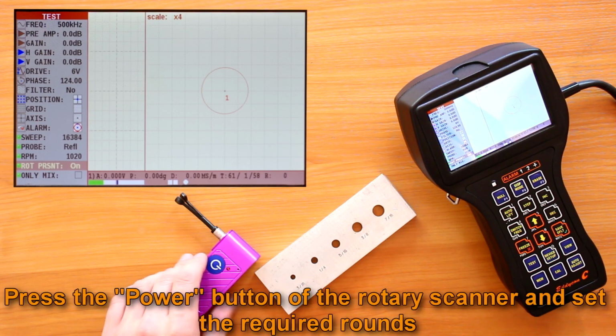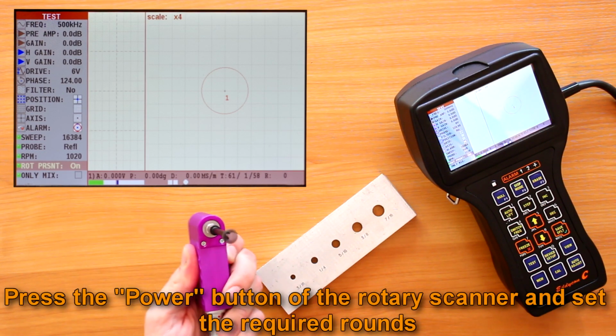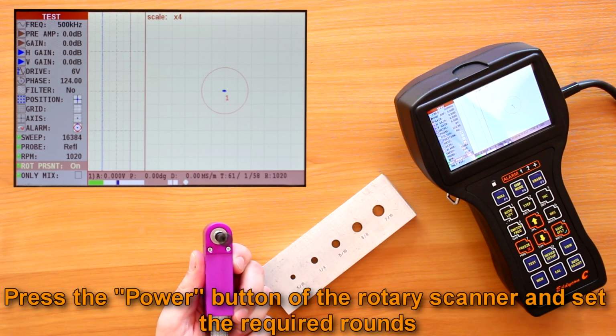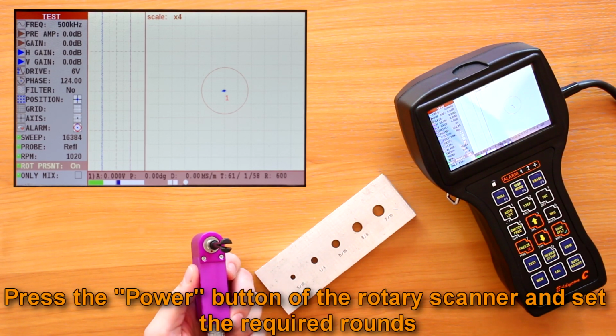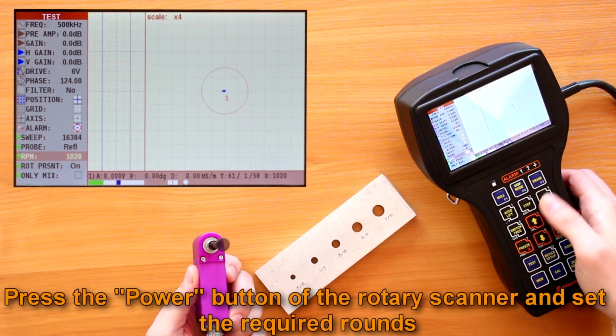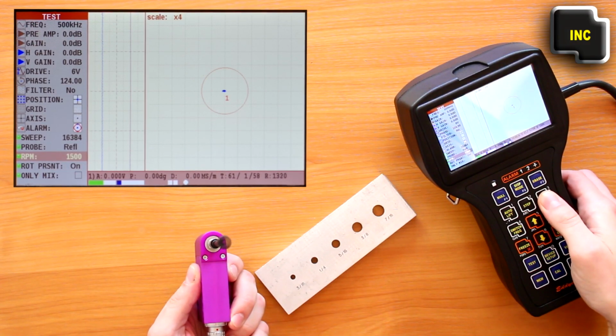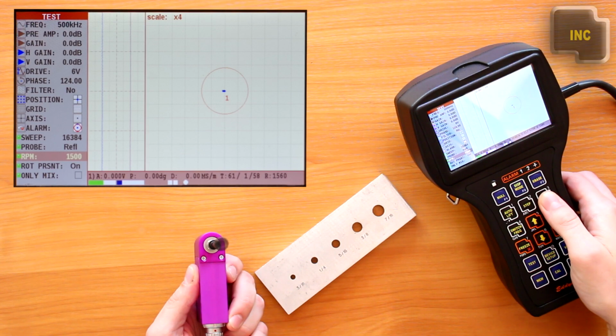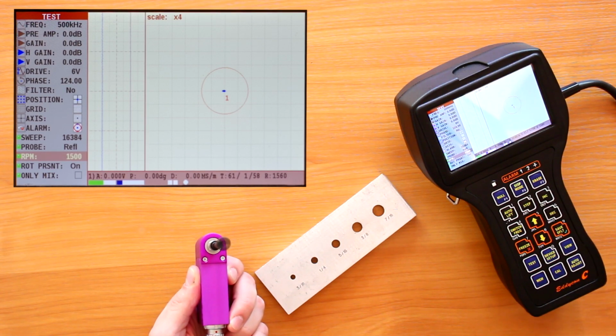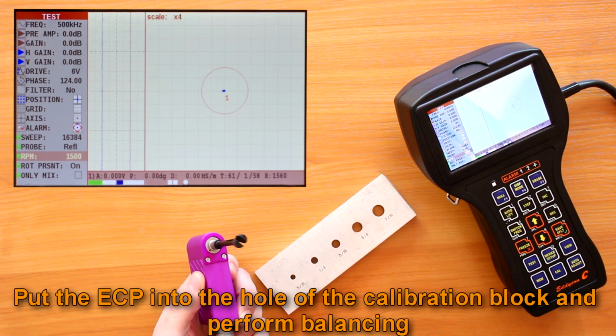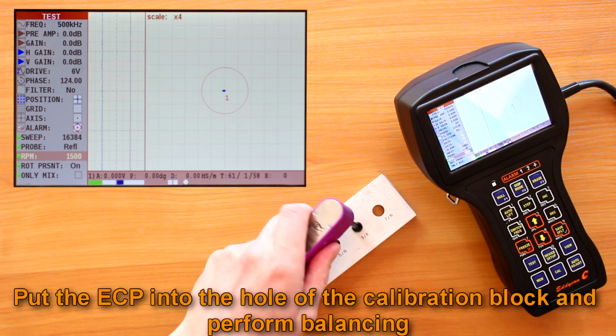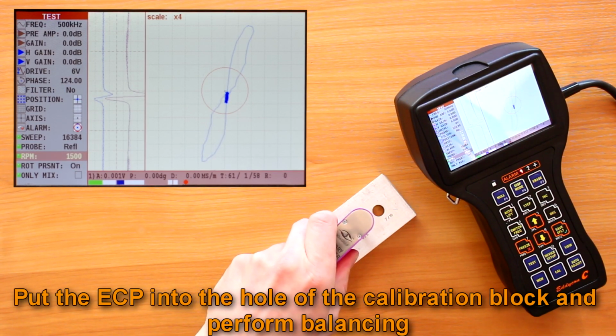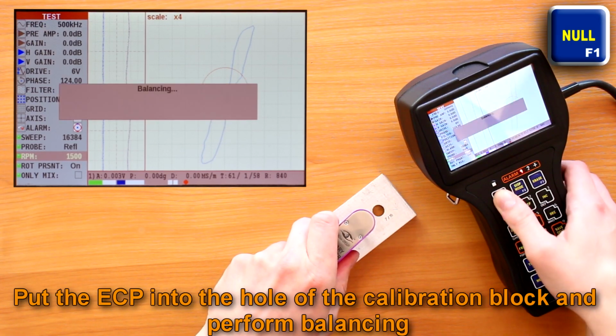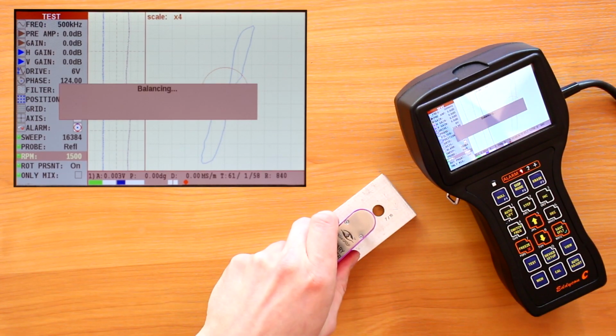Press the power button on the rotary scanner. Set the required rounds for the scanner. Put the ECP into the hole of the calibration block. Press the power button on the rotary scanner case. Press F1 to balance the ECP.